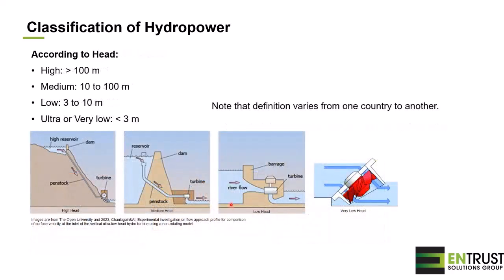The other important factor for classification is the head of the power plant, or rather the penstock, or the capacity of the plant. So we talk about high head, which is more than 100 meters. It's something that we can find, for example, in the Rocky Mountains. So this is typical of a high head. Low head is more what we can find, for example, along the Mississippi River. And very low head is rare, but it's for small projects where there's a high capacity of flow but very low head to drive a turbine.